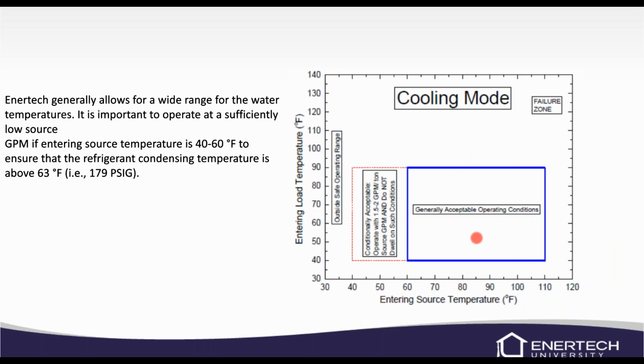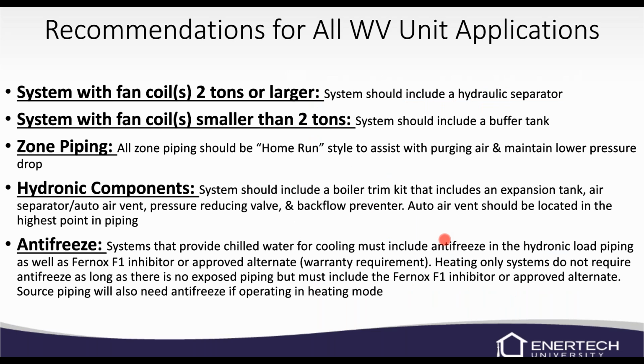Here's the cooling acceptable operating ranges. Recommended for all WV unit applications. Anytime you have a system with a fan coil that's 2 tons or larger, we recommend you install a hydraulic separator. If you have fan coils that are smaller than 2 tons, then we recommend a 40-gallon buffer tank.